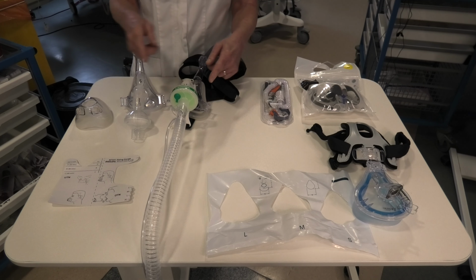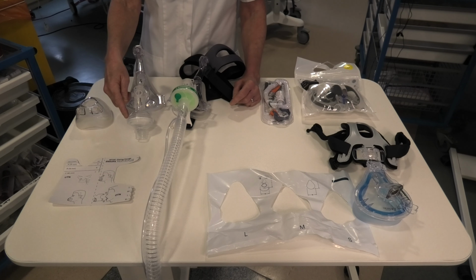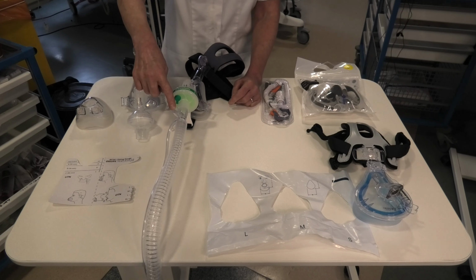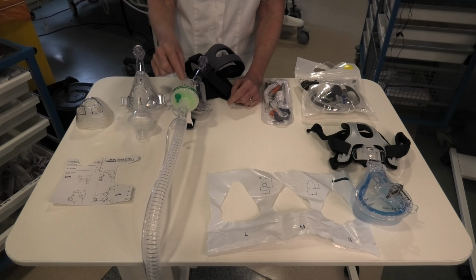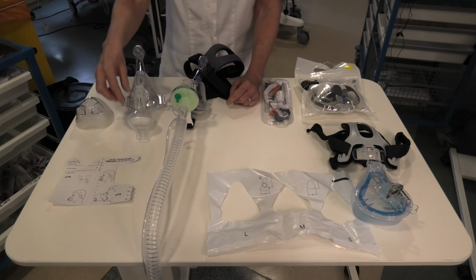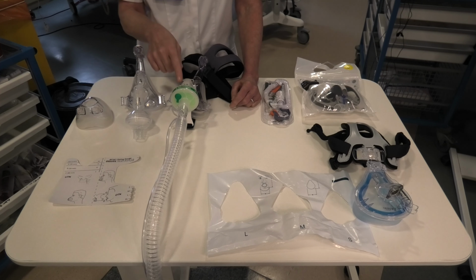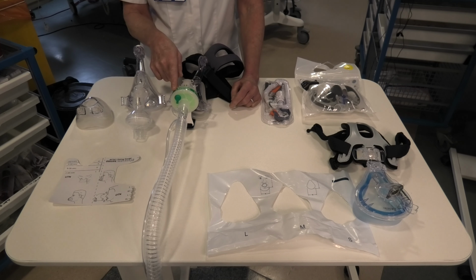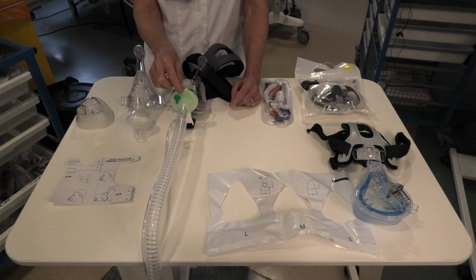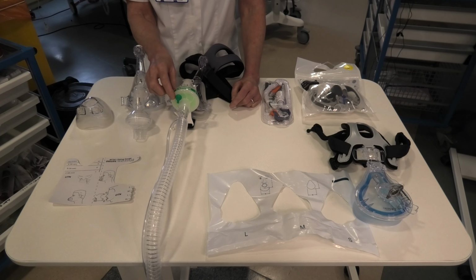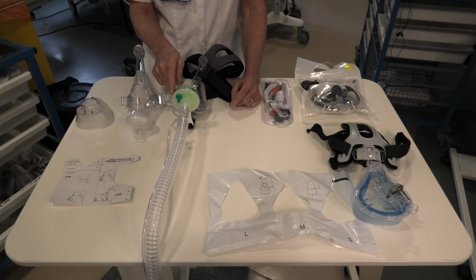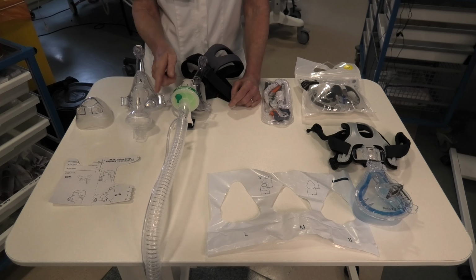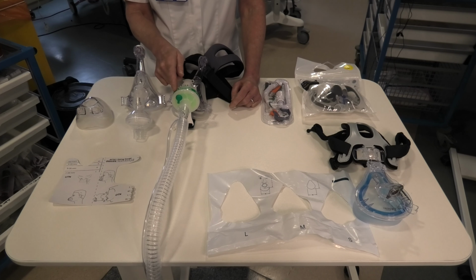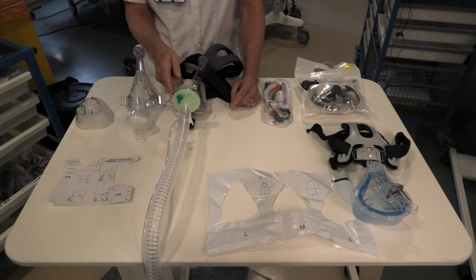Before you put a mask on somebody, you need to make sure that you have a filter in place. This is the exhalation port on the tubing that we use, but between the exhalation port and the mask you need a filter. We've got two different types of filter here. This is an antibacterial and viral filter. This is an HME, a heat and moisture exchange filter. The HMEs essentially catch heat and moisture from exhaled breath and then use that heat and moisture to humidify the next breath in. So they can really help patients not feel so dry, and again improves compliance. They must be changed. Both sets of filters need to be changed every 24 hours. This filter may need changing more often because sometimes they get wet.